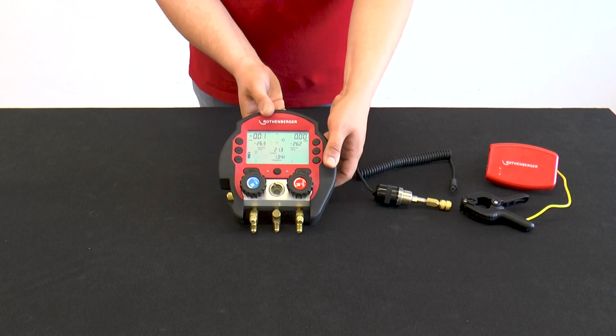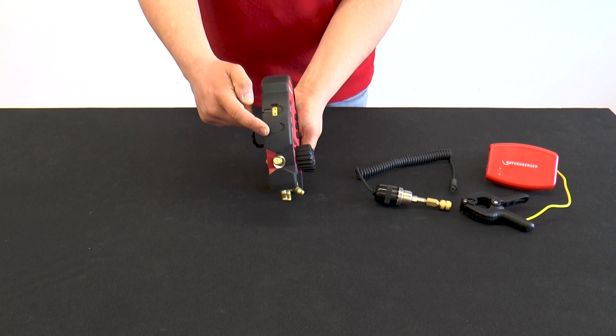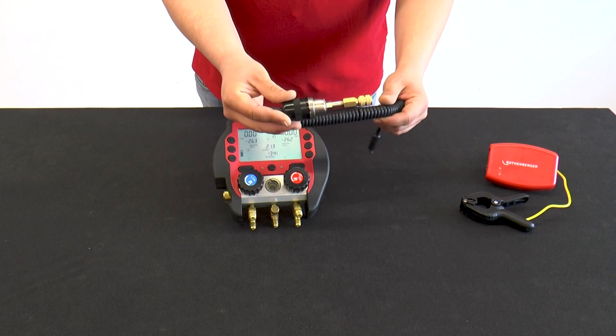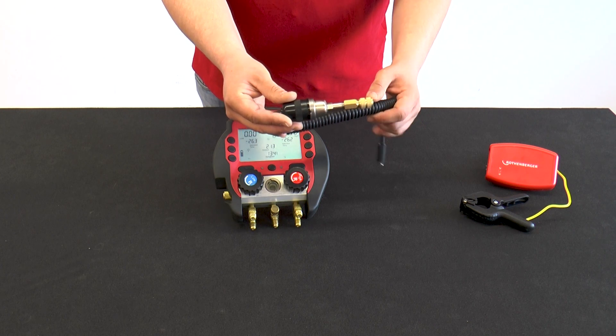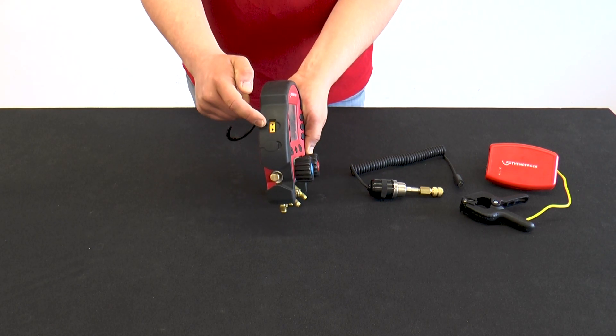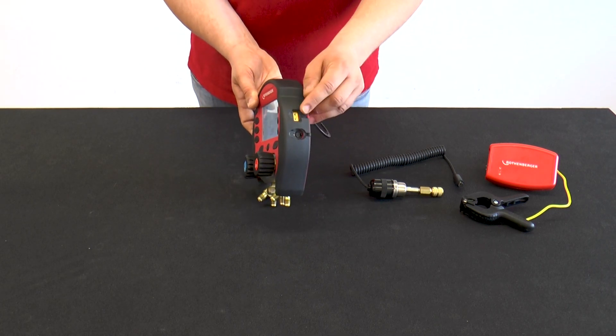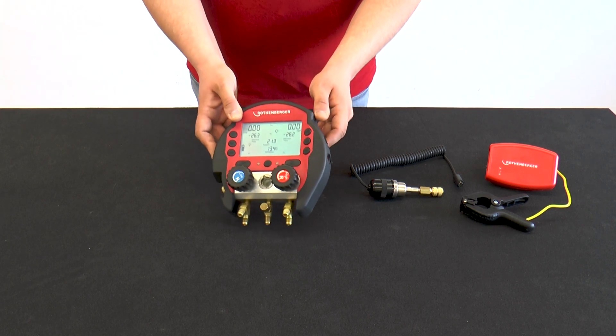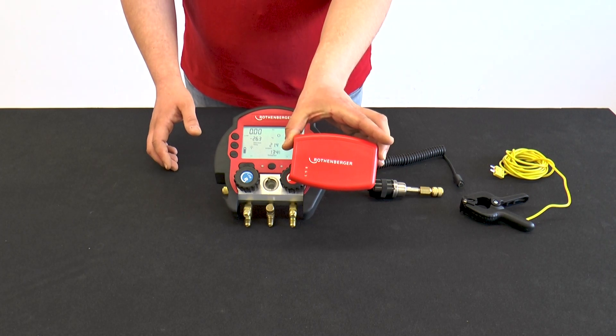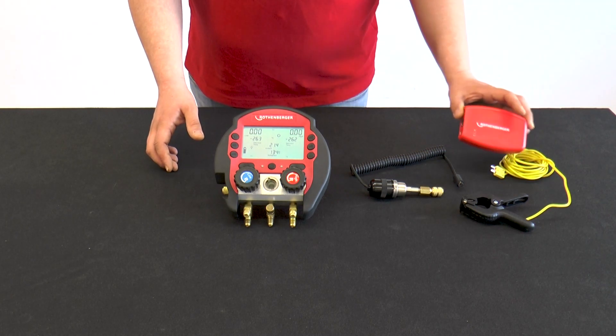If you look at the ROCOOL from the side, you will see various connection options. On this left side is, among other things, the connection for the external vacuum probe. The external vacuum probe offers the possibility to measure a vacuum up to four decimal places. Above this is the connection for a temperature terminal for the low pressure side. On the other side is the same connection for the temperature terminal of the high pressure side. Below this, there is a connection for our red box. The red box makes it possible to record refrigeration data of the air conditioning or refrigeration system for up to 96 hours.